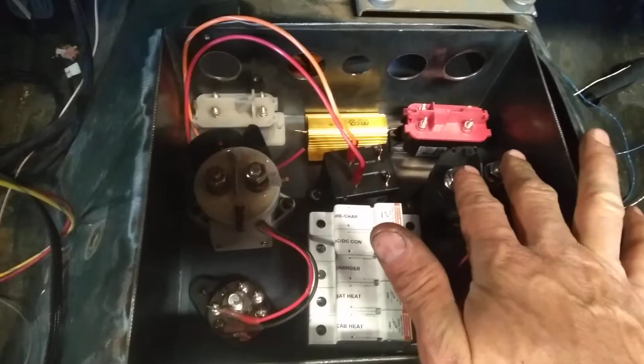It goes into the contactor in here, and whenever the BMS says yes, we're going to allow current to flow, it'll connect that contactor, and then current can flow through the positive battery junction terminal thingy there. And that's it. Then whenever it's time to make the motor run, this contactor will go, but it won't do it immediately. There's a pre-charge that has to happen to all the monster capacitors that are in the inverter, and that's what this little doohickey is for.